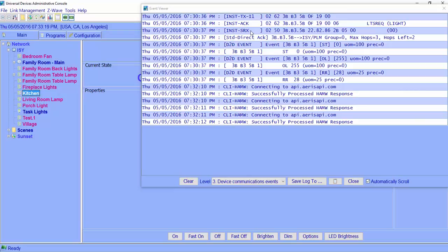And sure enough, you'll get to a breaker that you'll turn off. And keep in mind, after you've tested it, if you don't get a positive result, turn those breakers on and go to the next breaker. But eventually you get to a breaker where you've turned off something that was creating the noise that was preventing you from being able to talk to the device. And you'll all of a sudden start getting the response. So that'll at least narrow it down to the breaker that has the problem. So that's if we're looking for noise on the power line.